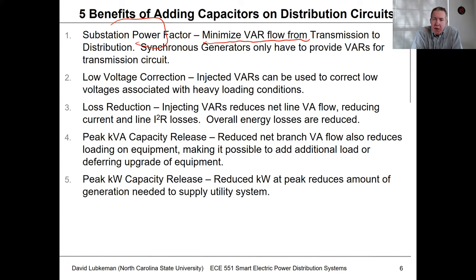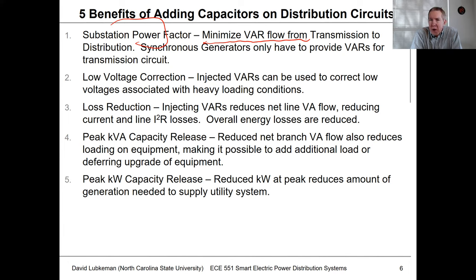Having generators produce reactive power limits the real power they can actually produce. We typically don't like to transmit VARs over long distances — VARs don't travel well because pushing them through a system causes voltage changes that are hard to manage. So we want to keep VAR flow from transmission to distribution as close to zero as we can.